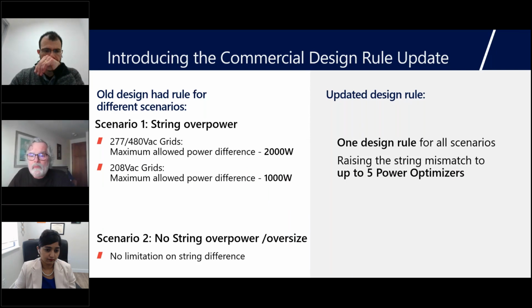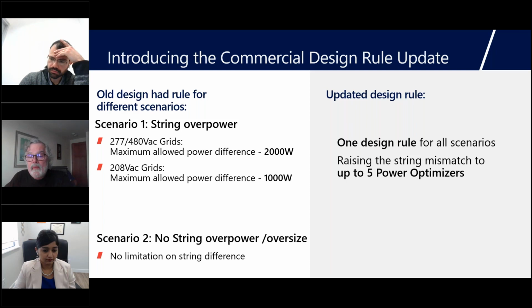And just to summarize the previous slide, we used to try to keep strings somewhat balanced to prevent them from current limiting. For our 480 volt inverters, we wanted to keep that delta at 2 kilowatts. For our 208 inverters, we wanted to keep that delta at one kilowatt. And if you were at the base power level that I was talking about earlier, we really didn't care about a delta. The power level would not cause the inverters to reach their current limits, so we were okay with no delta if you were not taking advantage of string oversizing. So now we've simplified that whole design rule situation by just making the delta between oversized strings at five power optimizers.